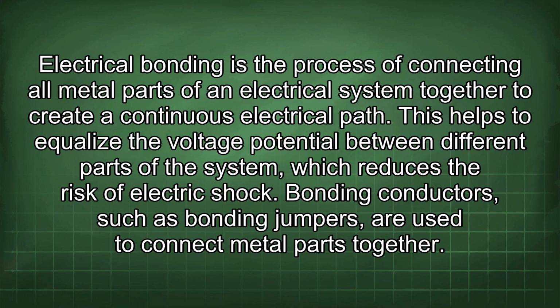Electrical bonding is the process of connecting all metal parts of an electrical system together to create a continuous electrical path. This helps to equalize the voltage potential between different parts of the system, which reduces the risk of electric shock. Bonding conductors, such as bonding jumpers, are used to connect metal parts together.